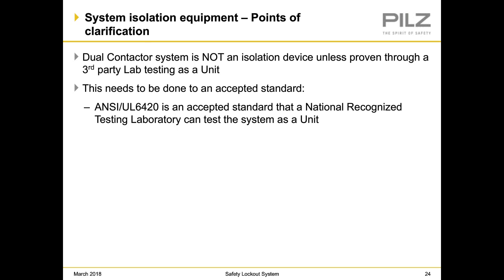You can buy a safety controller. You can buy contactors, safety-rated contactors. You can buy a three-phase safety voltage monitor from us and what have you. You can put all that together in a panel. But what it's not done is rated as a system. So again, all the standards point to everything being rated as a system and tested as a system. And keep in mind that, again, that's what we've done with this system. And the systems are sealed and only to be serviced by trained, qualified personnel. And we do have training programs and things like that as well to, again, qualify personnel at a plant to be trained to do servicing on that.